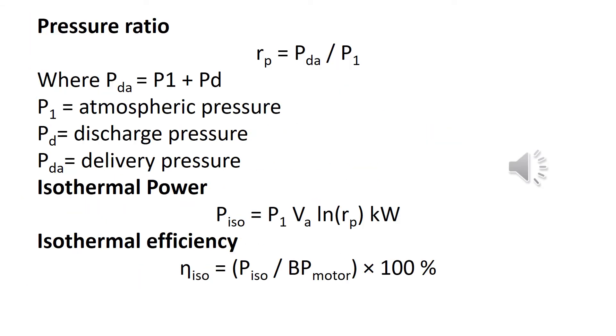Next, you have to find out the isothermal power, which is P1 × VA × ln(Rp), where P1 is the atmospheric pressure, VA is the actual volume of air compressed, and Rp is the pressure ratio — PDA / P1. PDA is the delivery pressure, which is the summation of discharge pressure and atmospheric pressure. Finally, isothermal efficiency is determined as isothermal power divided by the input power of the compressor (that is, the BP of the motor).